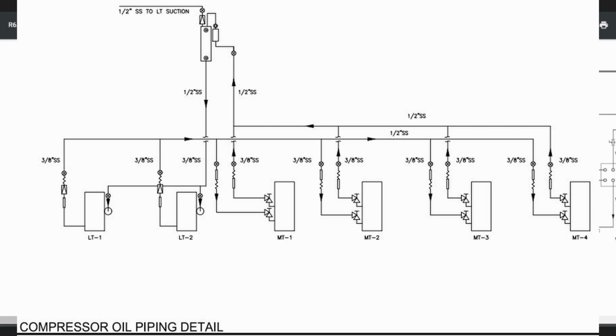Gotcha. And because this pressure right here is basically the same pressure, because it's basically using the same chamber, it's still the crankcase. And basically, because you're sucking off of the low temp, that's what's going to drive all this in through here, correct? You lost me there. The oil from the low stage compressors leaves the compressor at about 52 or 53 pounds, let's say. And it goes into a line that's pressurized to 52 or 53 pounds through a cap tube. Then the only reason the cap tube is on the low stage is to create an intermediate pressure so that if one compressor has a little bit higher oil pressure than the other, say one's at 52 pounds and one's at 50 pounds, then all your oil would come out of one machine, and we don't want that.